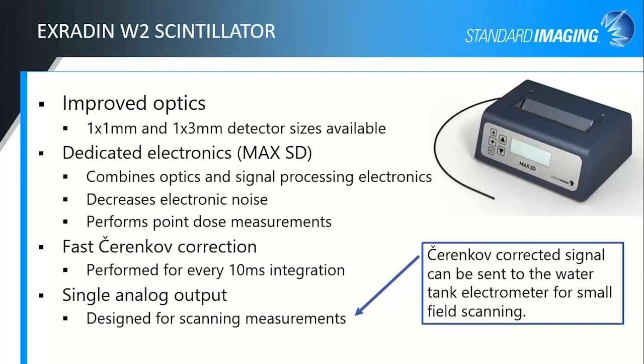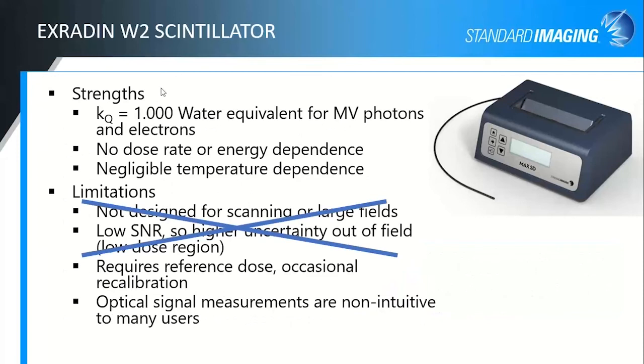You can perform point measurements directly with the Max SD if you're trying to do output factors or something like that. But it also does a very fast Cherenkov correction and can convert that corrected signal into an analog output so that it can send it out to the electrometer on your scanning water tank, for instance, so that you can hook it up as a kind of 2-stage intermediate in the input channel of your water tank. And your water tank doesn't know that it's any different from a diode. You don't apply bias to it, but you get signal when it's irradiated. So we kept the strengths of the W1. We didn't lose anything with that, but we were able to cut out a couple of those limitations when we went with the W2.